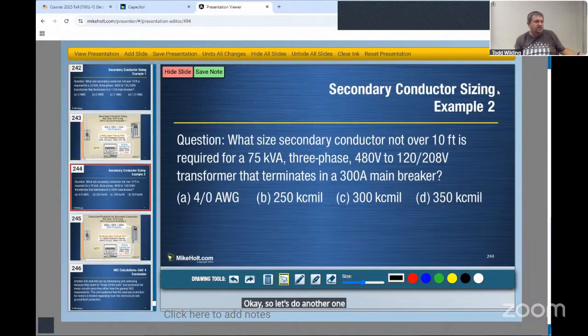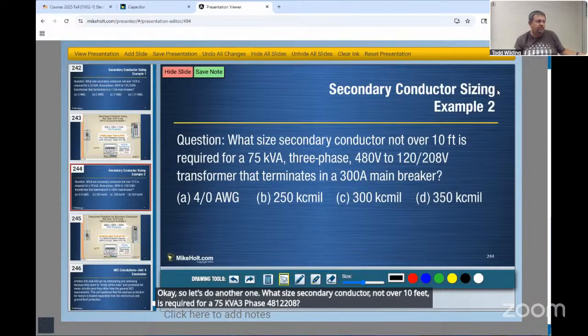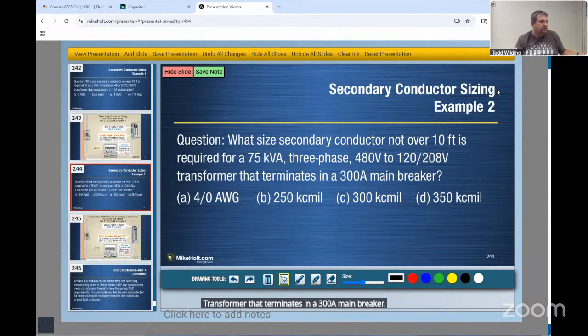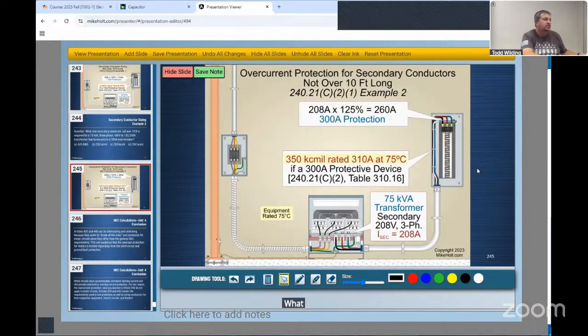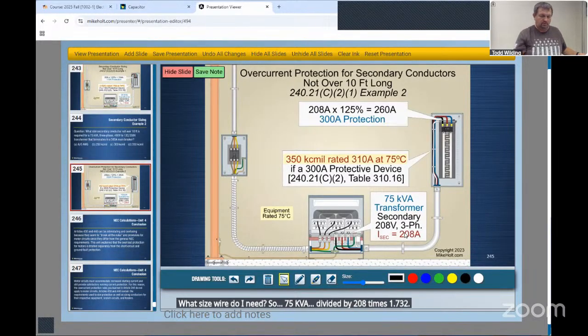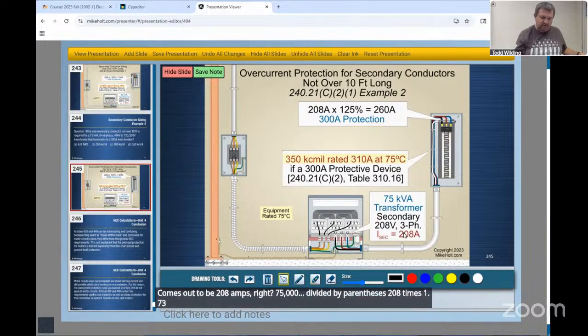Okay, so let's do another one. What size secondary conductor not over 10 feet is required for a 75 kVA 3-phase 480/120/208 transformer that terminates in a 300 amp main breaker? Okay, so now I'm still using 450.3(B) primary and secondary. What size wire do I need? So 75 kVA divided by 208 times 1.732 comes out to be 208 amps, right? 75,000 divided by parentheses 208 times 1.732 parentheses equals 208.185 amps. So 208 amps.